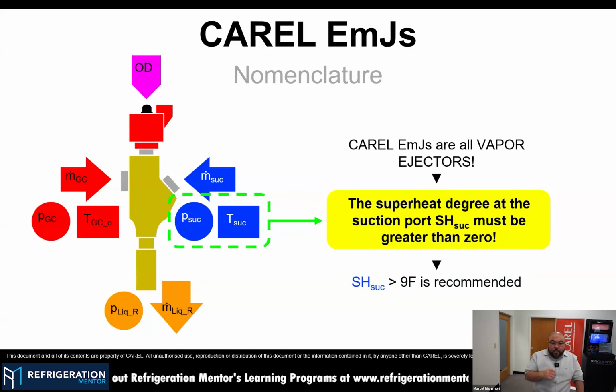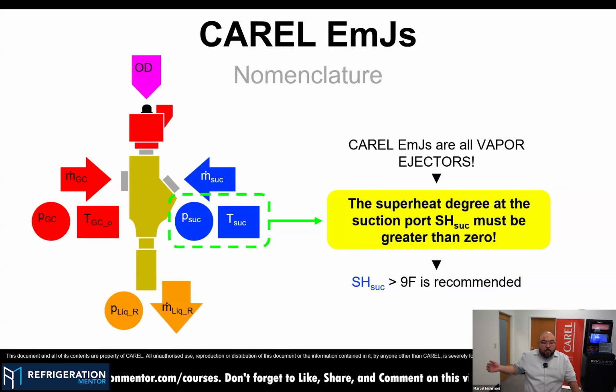And as I mentioned, we have an ejector that is vapor-based only. So the geometry of the ejector is optimized for dragging vapor only. It would work if we have small droplets of liquid inside the ejector, so low superheat, but its maximum efficiency, so maximum capacity of dragging refrigerant, occurs when we have just vapor on that specific line. As a general rule of thumb and recommendation, we would like to have a superheat higher than 9 F as a reference at the inlet of the suction port of the ejector, okay? It means that on the case side you could have a lower superheat, because from the case until it comes to the rack, you could increase this total superheat a little bit, okay?